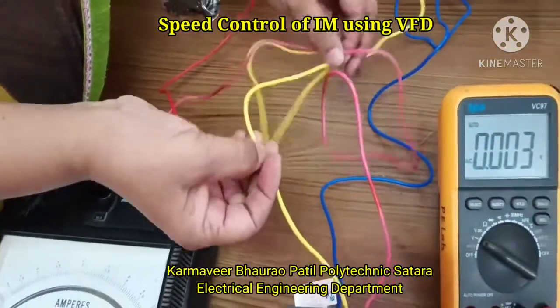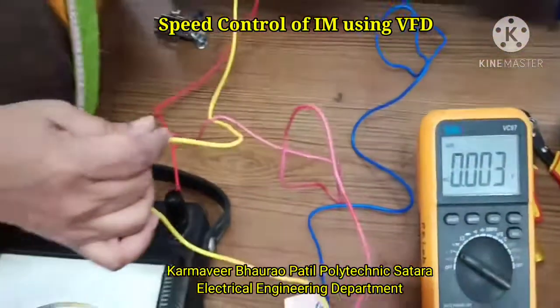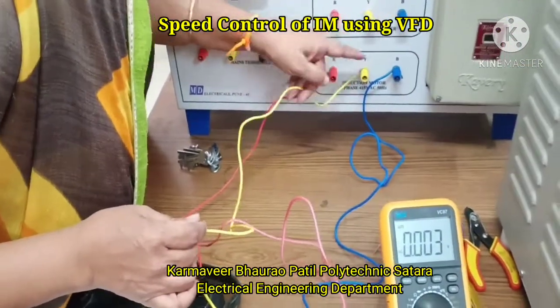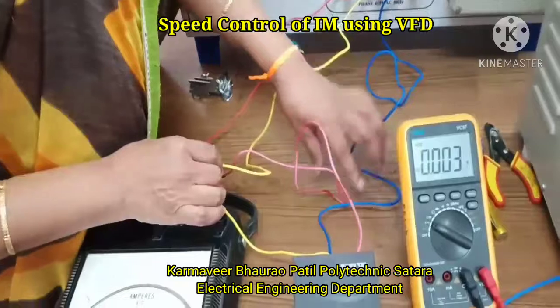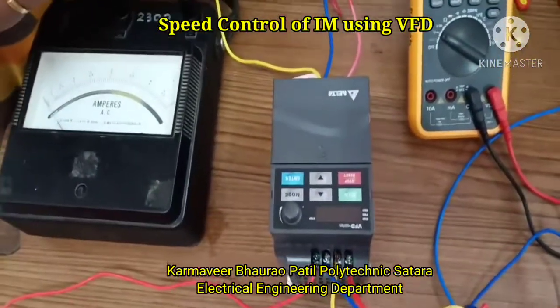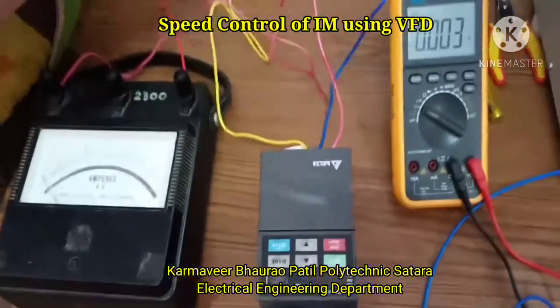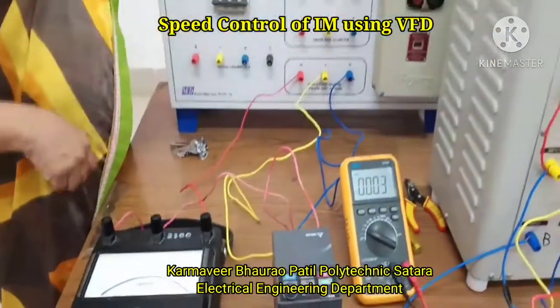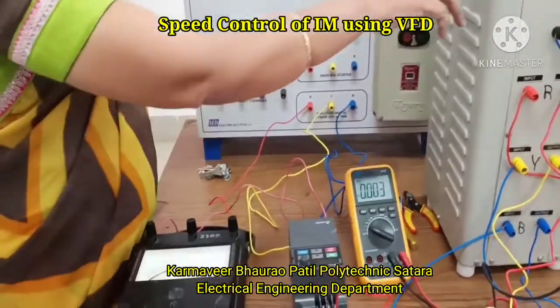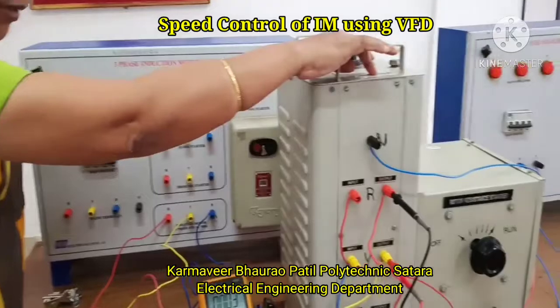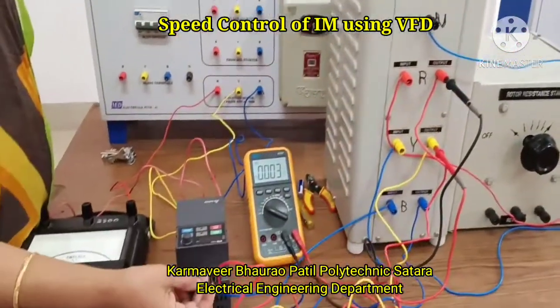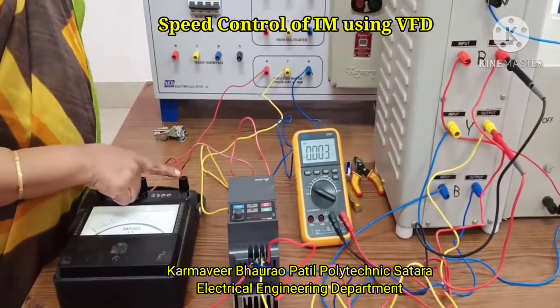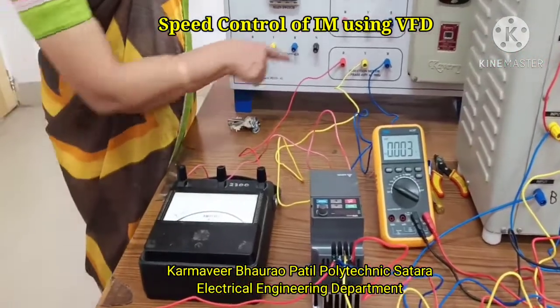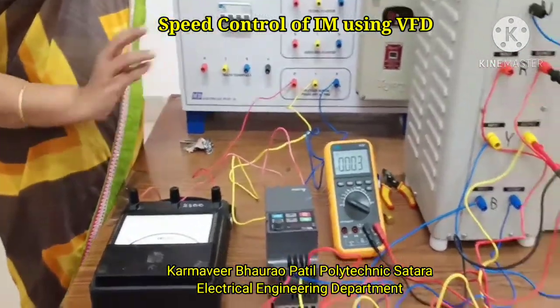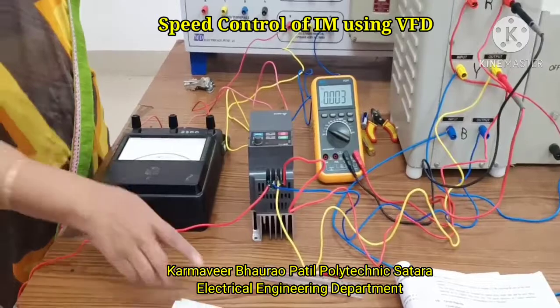The Y terminal of the output of the VFD will be connected to the Y terminal of the stator of the squirrel cage induction motor, and the B terminal will be connected to the stator B terminal. So everywhere the R phase runs from the supply to the auto transformer input, the auto transformer output to the VFD input R, and the VFD output R goes to the ammeter, whose second terminal goes to the stator. Like that, we also connected the Y phase and B phase.